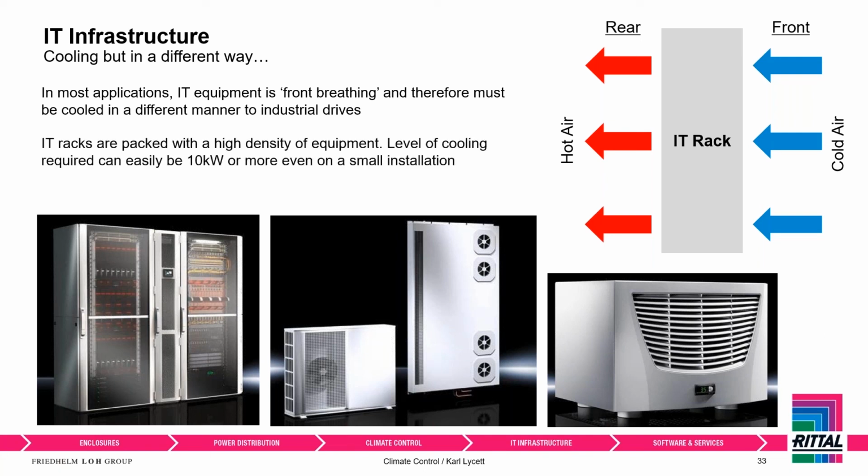Again, IT racks are very highly dense with equipment, and IT equipment emits a lot of heat. When we're looking at heat losses, it can be 10 kilowatts with a couple of servers in there, and I'm not joking on that. It can be a lot higher, even on a small rack in a broom cupboard. So IT is a lot more about liquid cooling, a lot larger heat exchange and things like that. So Rittal has a full catalog section just on specific IT cooling equipment.